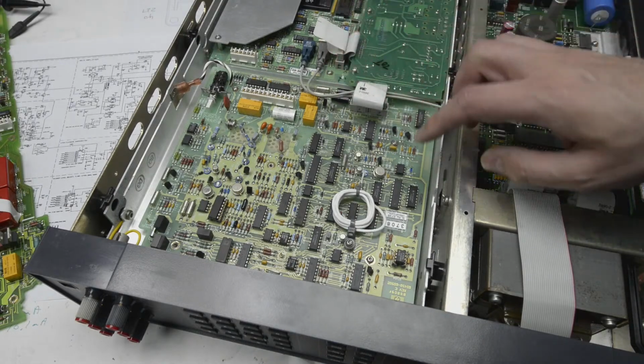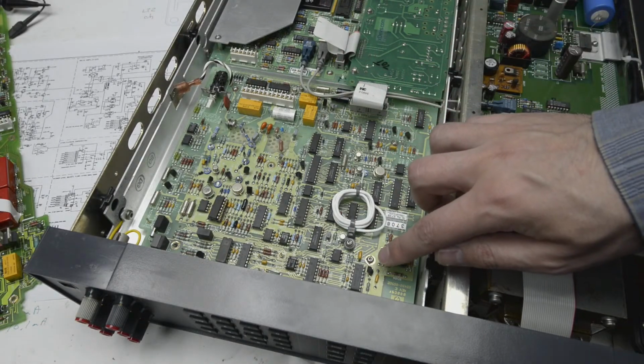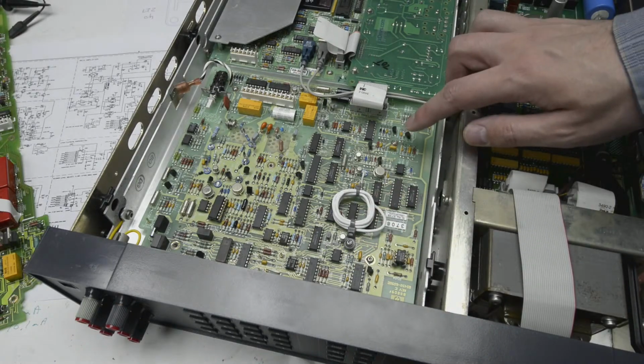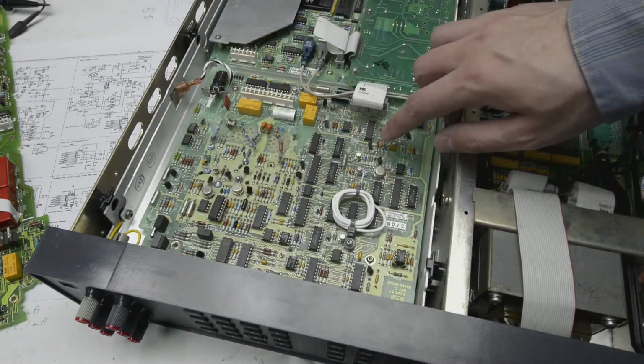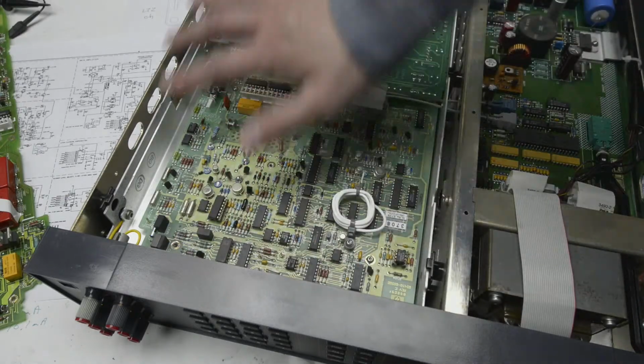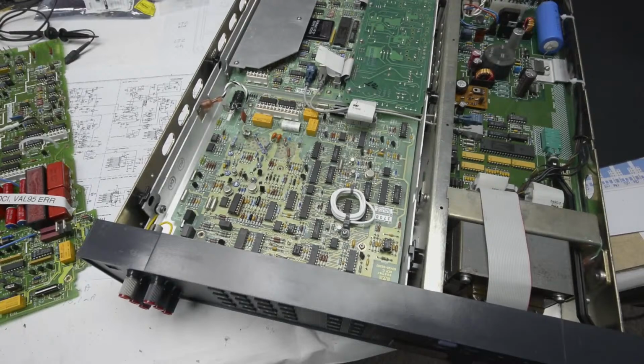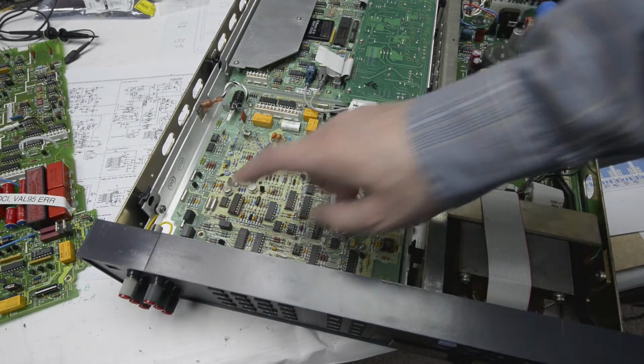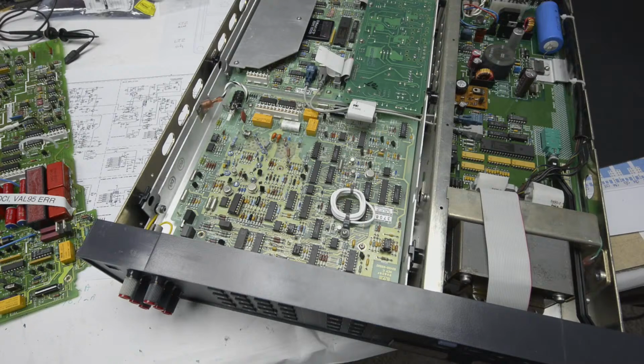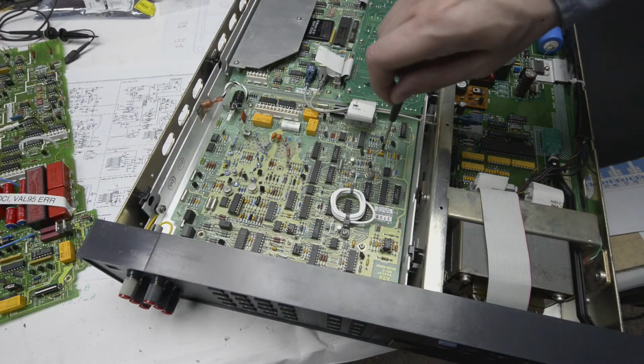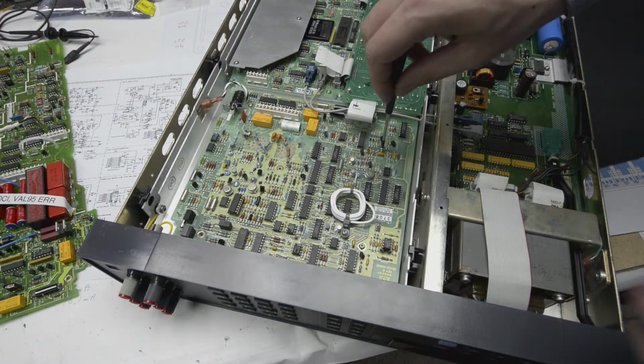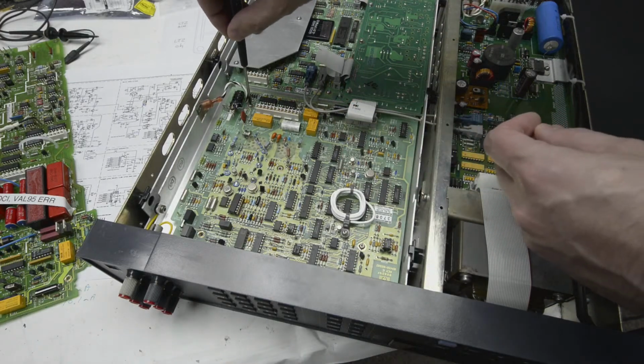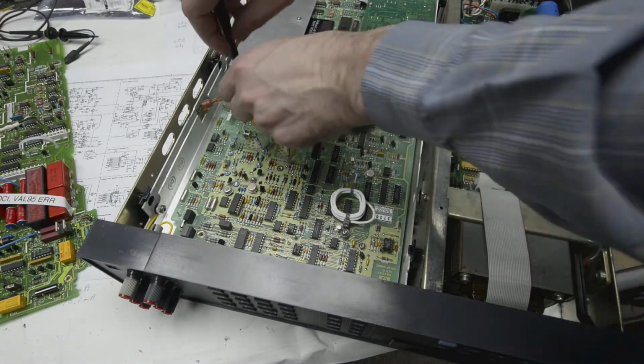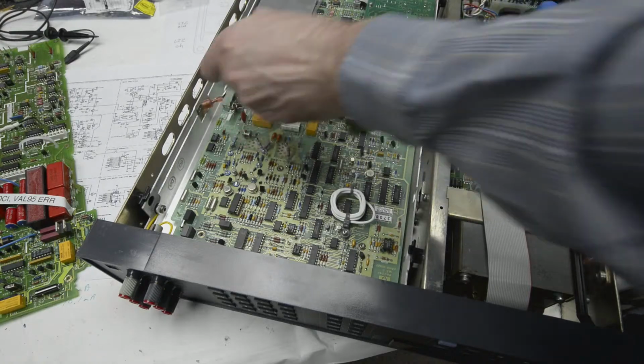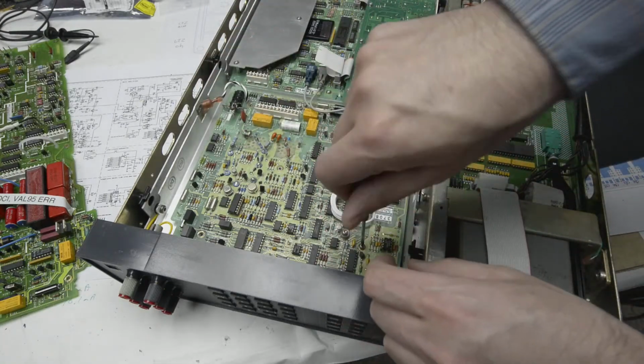An actually interesting experiment is, I see these posts or the pads for mounting the screws. They actually have electrical connections as well, because all this metal casing is actually at the guard potential. So if you don't have the screws in, would it have any fail, like a hardware fail? Let's try that. I'll just remove the screws, lift the board a little bit, so it doesn't have contact with the metal stud. And we can power it up and run the self-test and check the AC ranges.